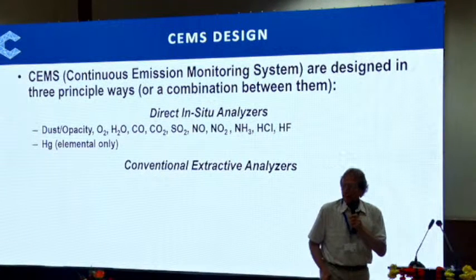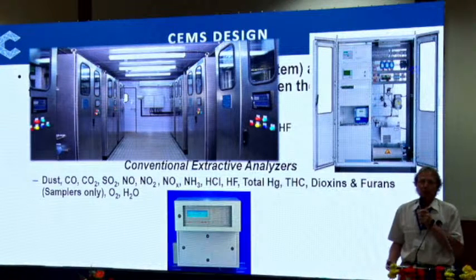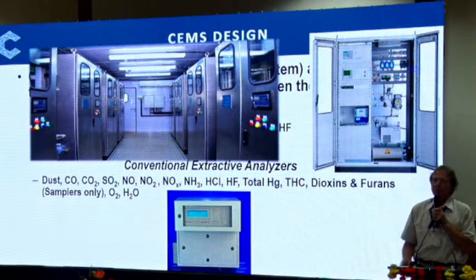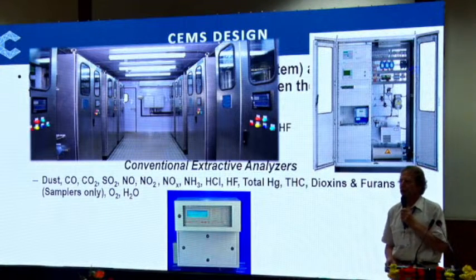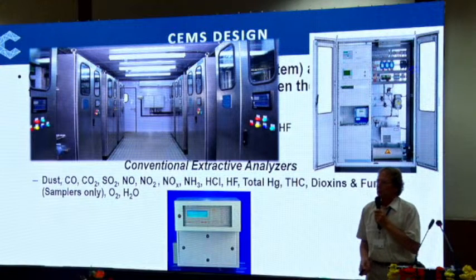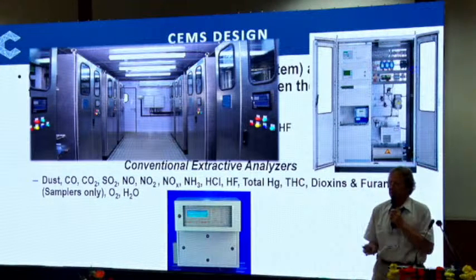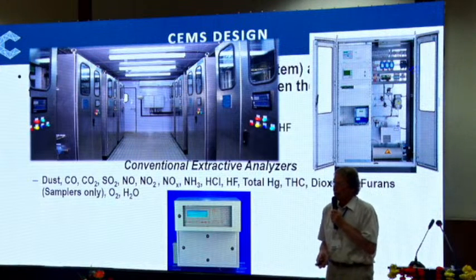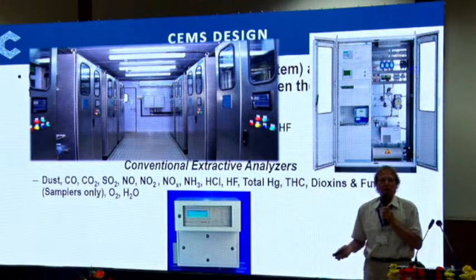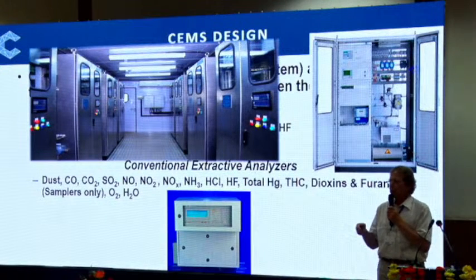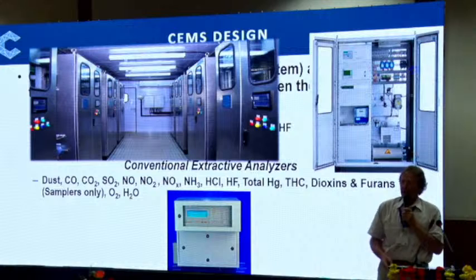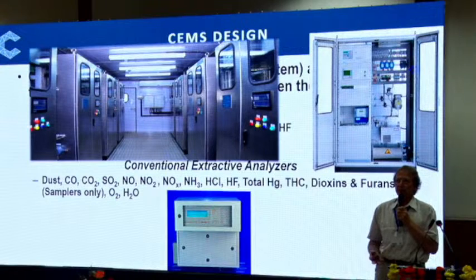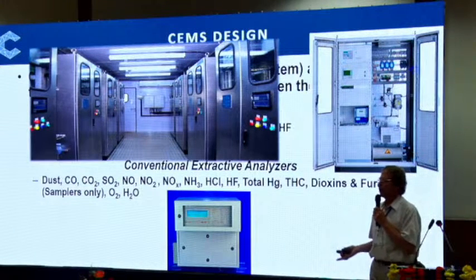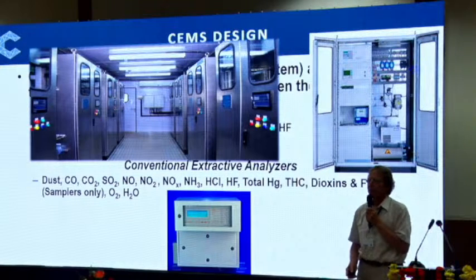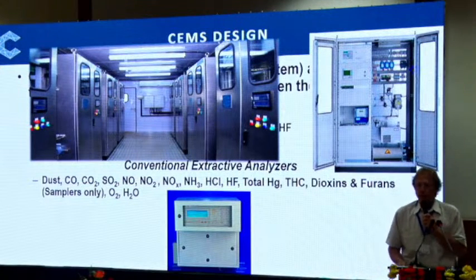Conventional extractive analyzers take out the sample. That is possible for dust. As we have seen, Sanjeev showed the extractive beta gauge this morning, or the extractive light scattering instrument for wet stacks. This is for dust. Then all the gas components, total mercury, total hydrocarbons, dioxins and furans I mentioned here. And as you see the words in the brackets behind, we're talking about nanograms per cubic meter that need to be detected, so there are no analyzers around. It's, quote, unquote, only samplers. And of course, oxygen and humidity.